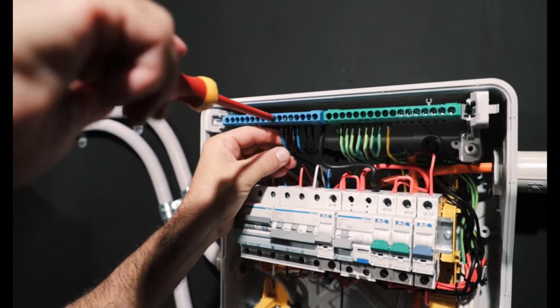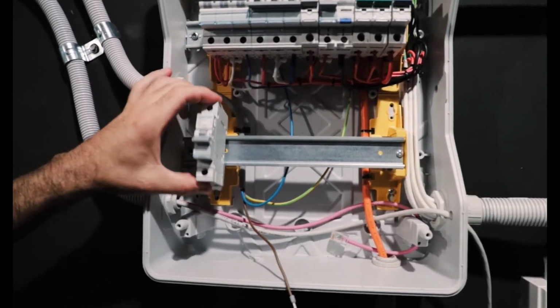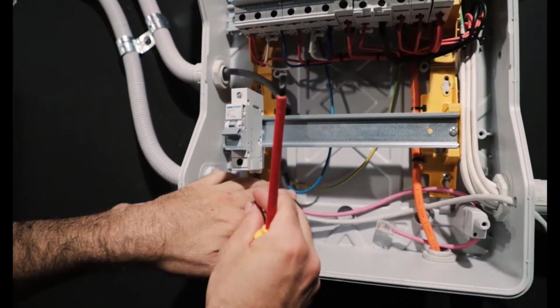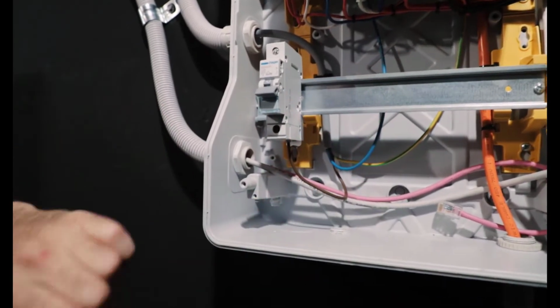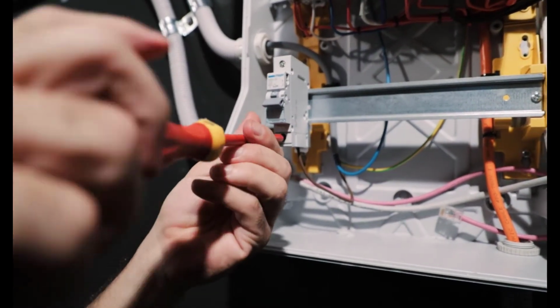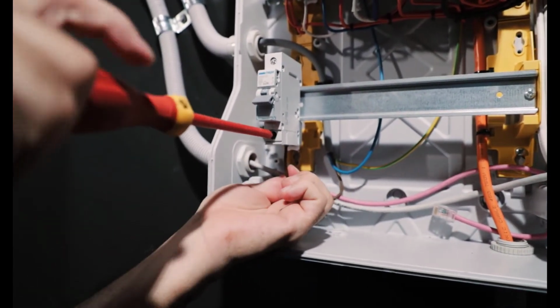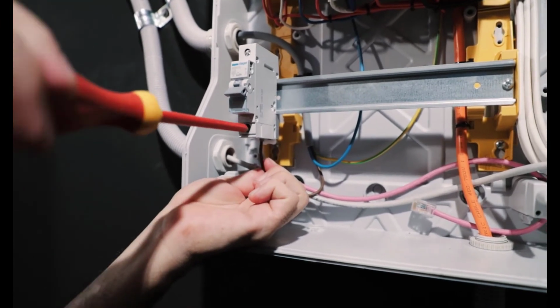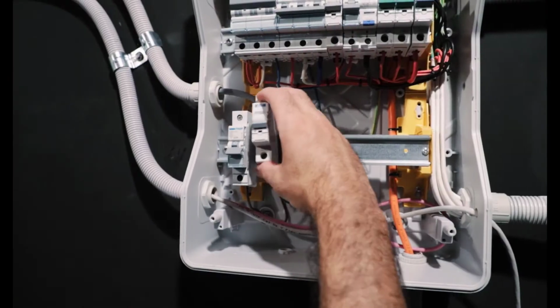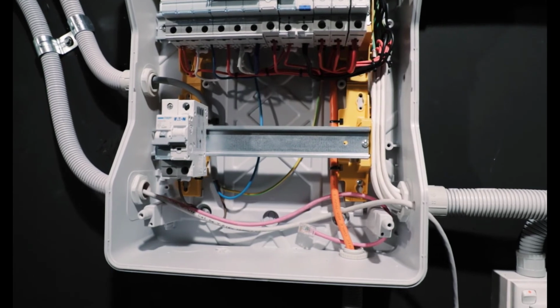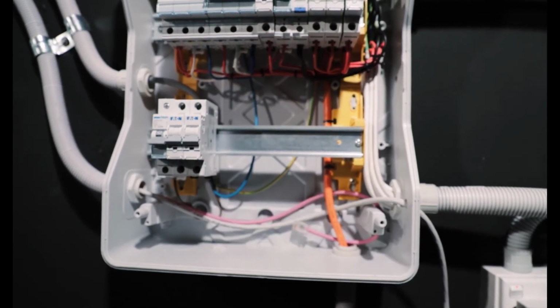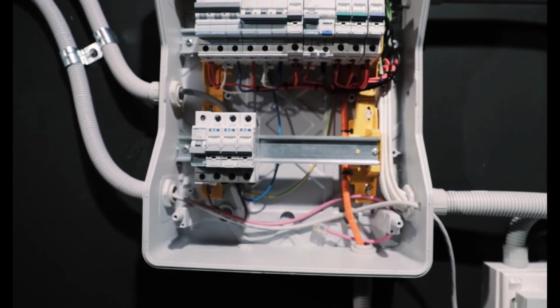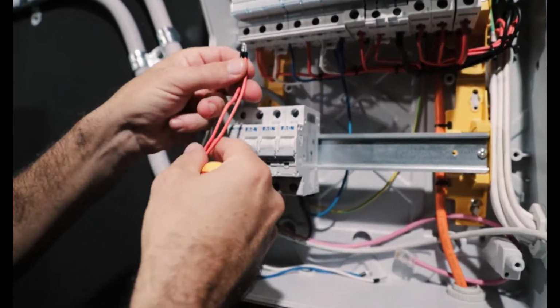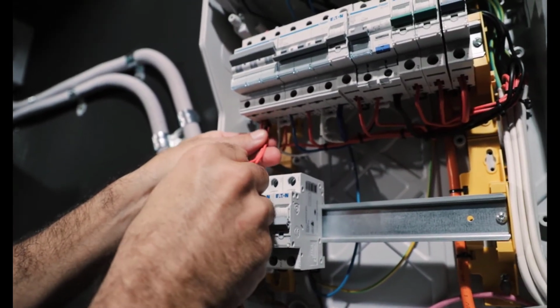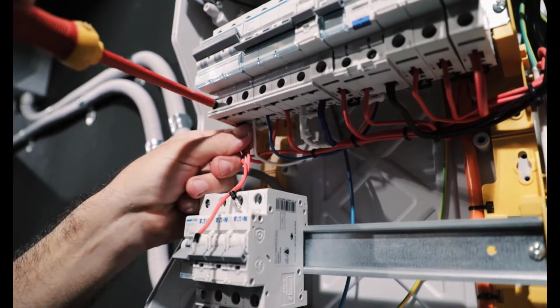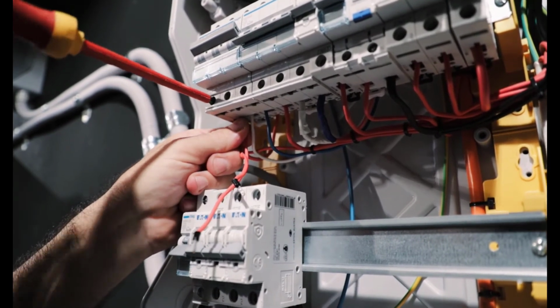If, however, let's say you had a PV system on L2 and you had your Sonnen on L1 or L3, doesn't really matter, you'd still be able to allow for that production to be able to be utilized for charging if the production is greater than the load. All the Sonnen system is actually going to be doing is aggregating all the values. Now, given this is then obviously a 3-phase meter setup, we're going to need 3 isolators, 1 per each phase.